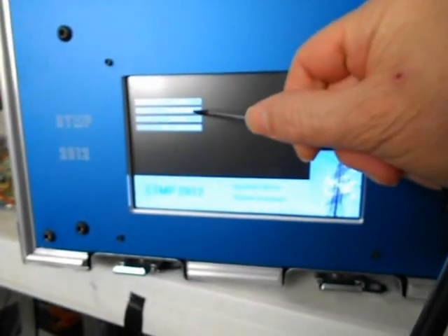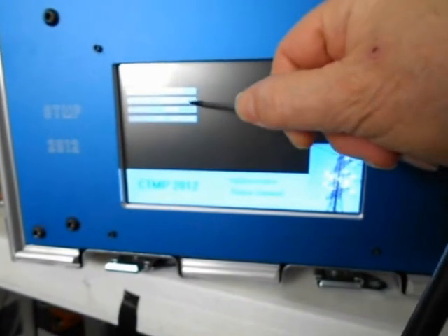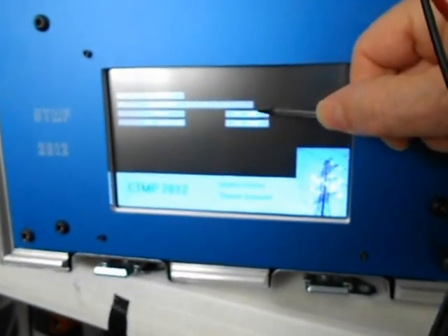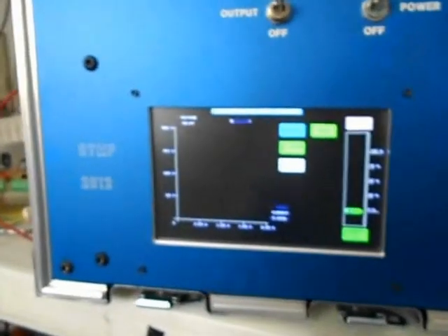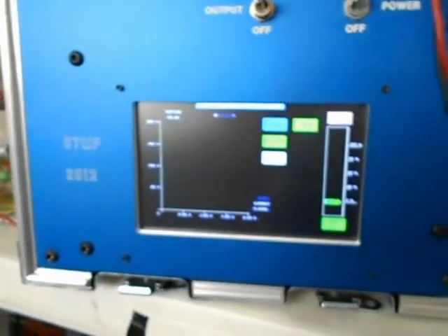Okay, then let me check the saturation. The other test we want to do on a CT is saturation, and I happen to know this will saturate at 200 volts. So I select saturation 200 volts. Back over here on the spreadsheet, I'm going to put the start block. I'm going to click on A10 because that's where the data has to start to fill in the graph properly. It's very important you be on A10 or else the results may be scrambled.